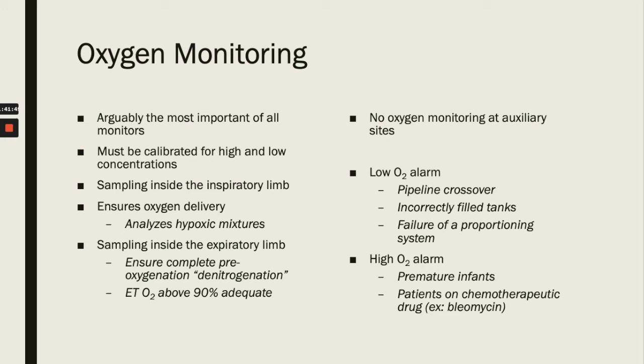failure of the proportioning system, where our proportioning system allows us to go down to a specific proportion of a ratio of oxygen to any other gas while we're giving another gas. And if that proportioning system fails, then we know that a hypoxic mixture is possibly being given to the patient, or we have no oxygen, or we've lost oxygen. And that'll alert the O2 alarm.